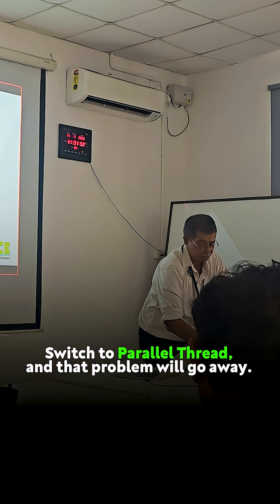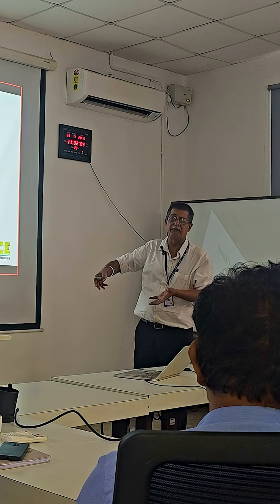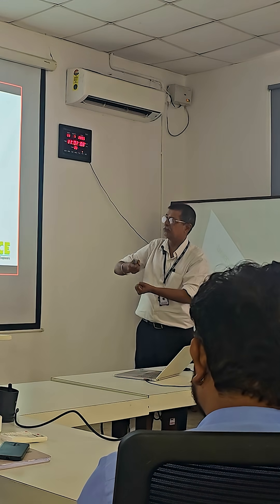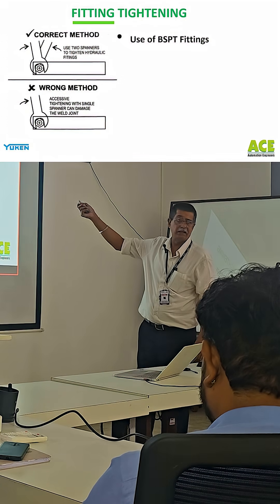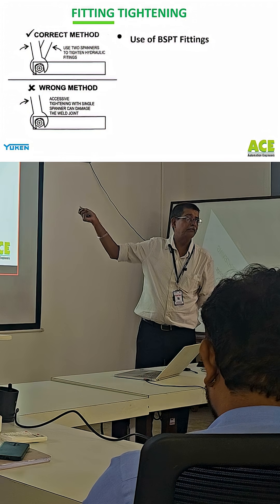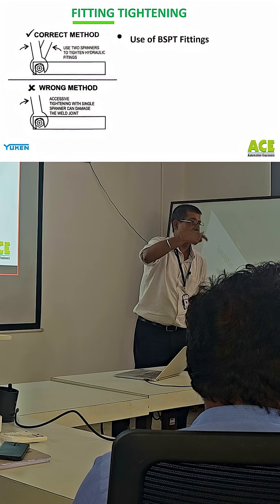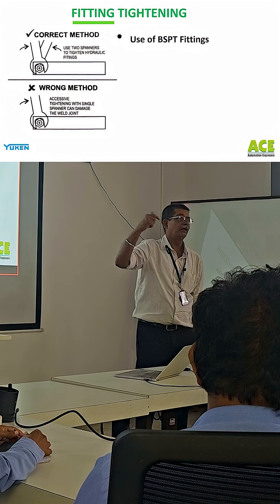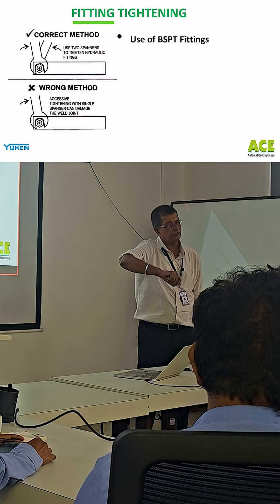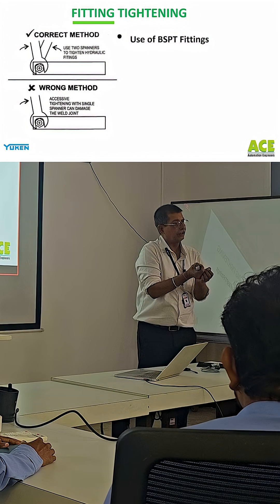So if we switch to parallel thread, that problem will go away. We have to teach our technicians, at least here in the factory, that we must use two spanners — it's a very important step. I have written about the use of BSPT fittings: if it is taper, then please use taper. That's another problem — probably not happening with Yuken, but it does happen that it's a taper thread but guys will try to use a BSP thread and then only two threads will engage.